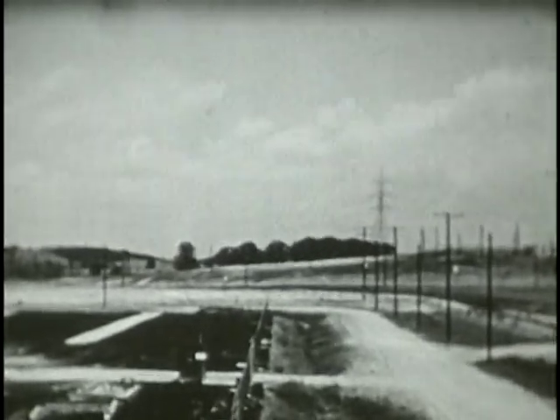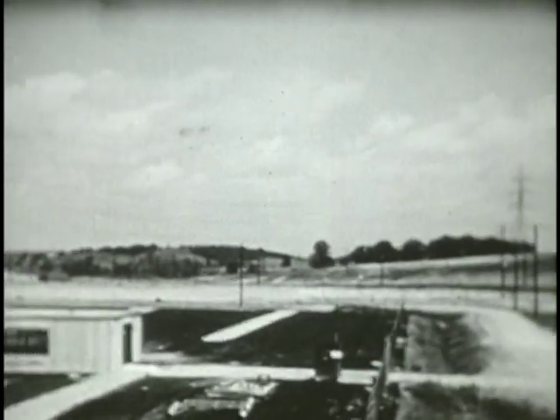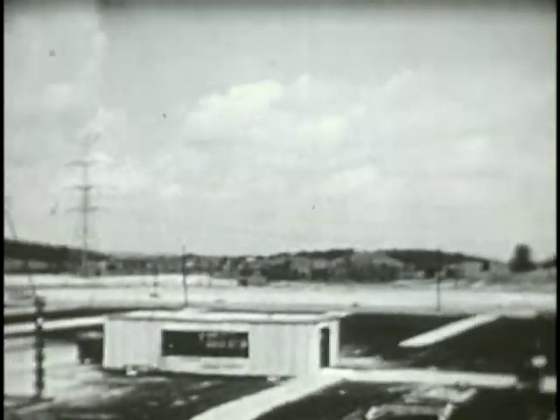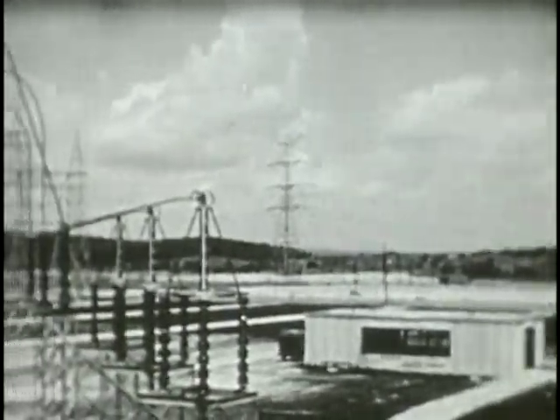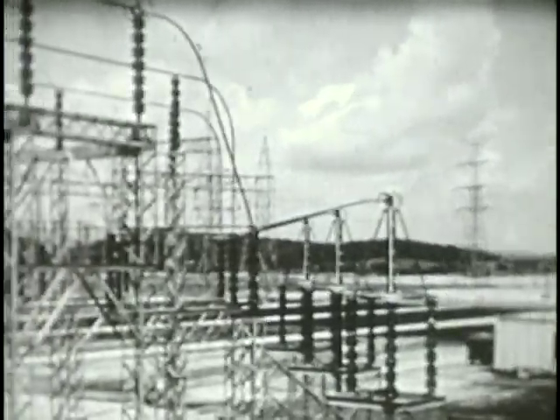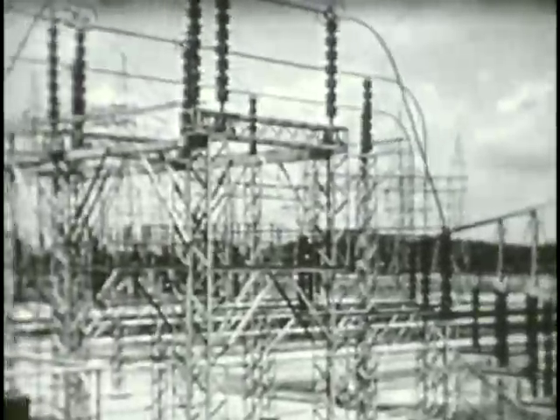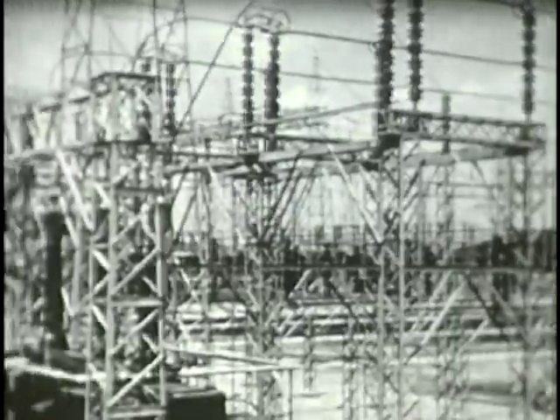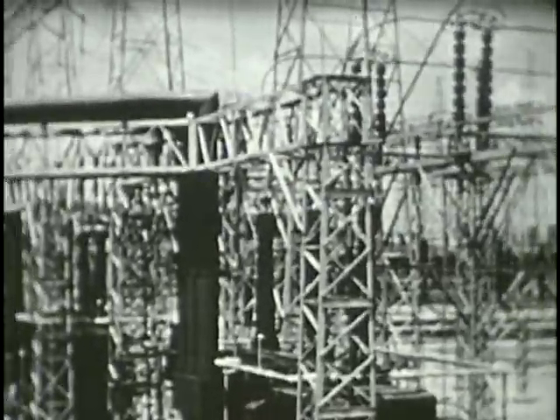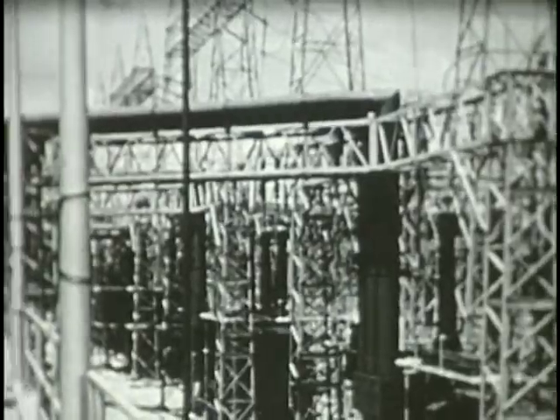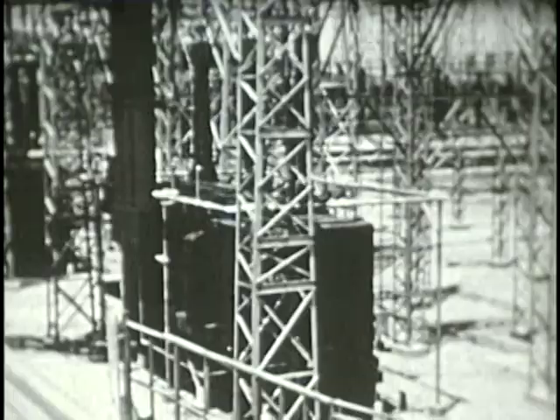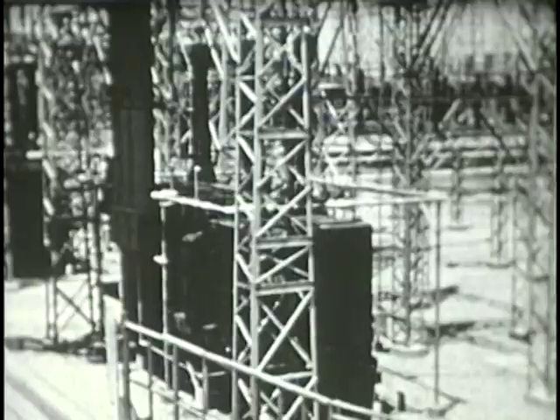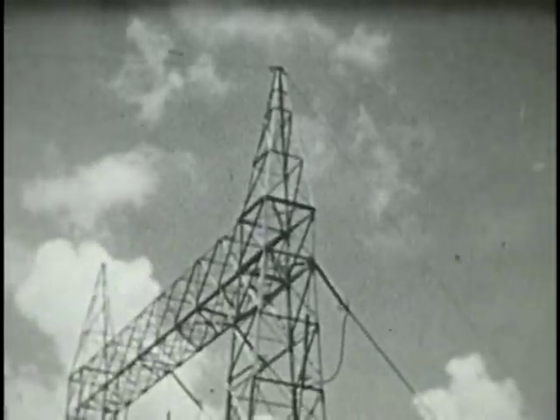Transmission of this power from each plant is made over 2 double-circuit lines at a nominal 330,000 volts, equal to the all-time high-voltage record in this country. Each of the circuits has a capacity of 1 million kilowatts for line sections of 50 to 75 miles in length. At the plant, the circuits feed into substations, which consist of switch yards, switch houses, and control houses. Switchyard design is based on the double bus arrangement and the breaker and a half switching scheme. Towers are of the vertical lattice type columns.